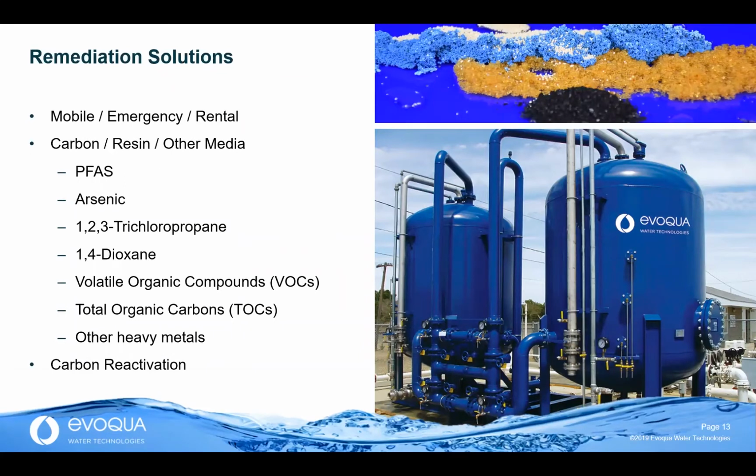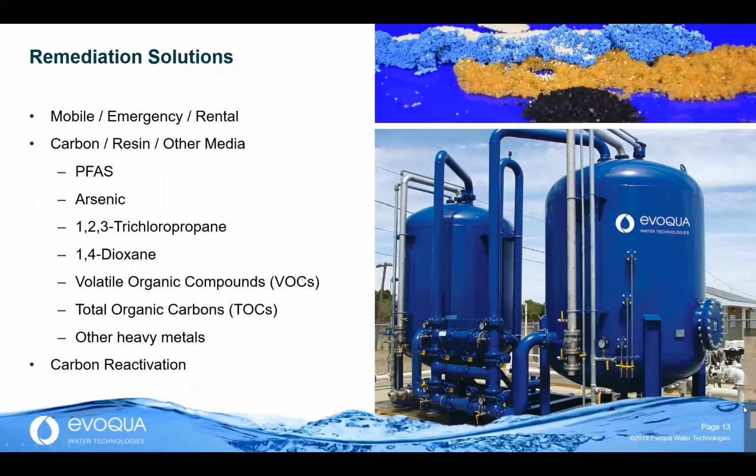Once again, if you're using carbon in these vessels, it can be reactivated and reused, either brought back to the site if it's a municipal site through our NSF or someone's NSF reactivation and certification process, so you get your carbon back every time, as well as some made up carbon, so to speak. When I say made up, I mean virgin carbon made up for any attritional losses of the carbon, to make sure you're getting back a full load of what you sent out.